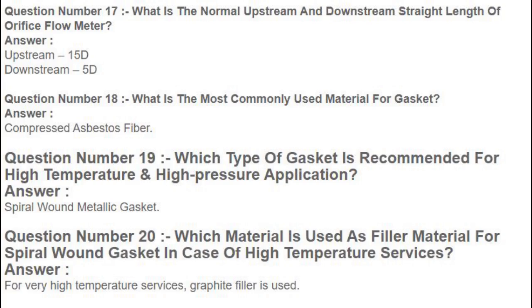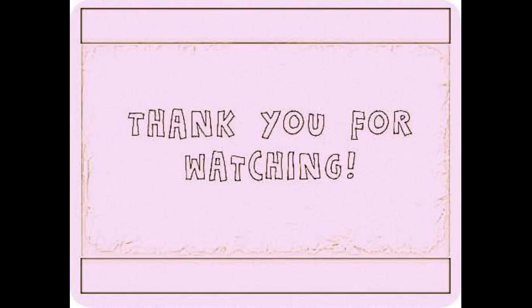Question number 18: What is the most commonly used material for gaskets? Answer: Compressed asbestos fiber. Question number 19: Which type of gasket is recommended for high temperature and high pressure applications? Answer: Spiral wound metallic gasket. Question number 20: Which material is used as filler material for spiral wound gaskets in case of high temperature services? Answer: For very high temperature services, graphite filler is used.